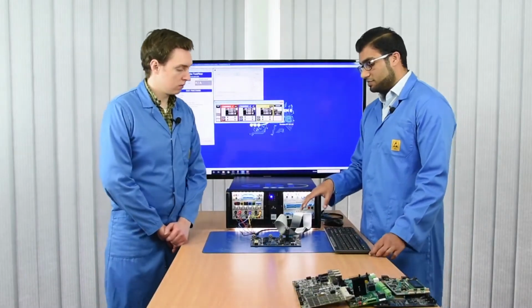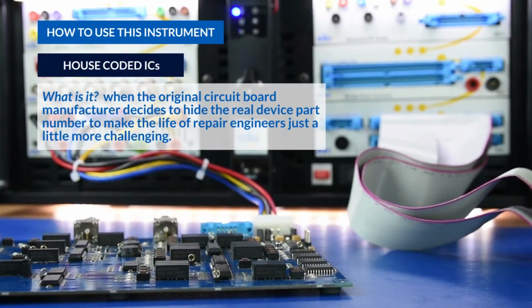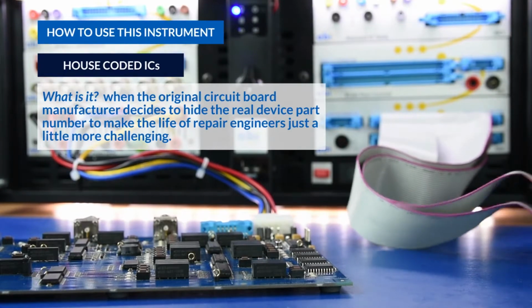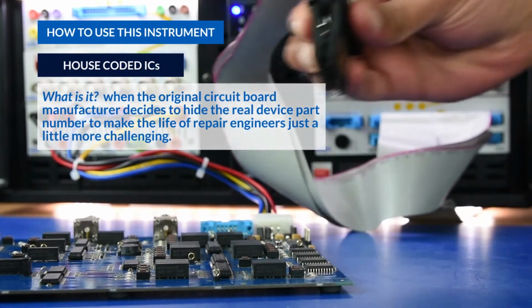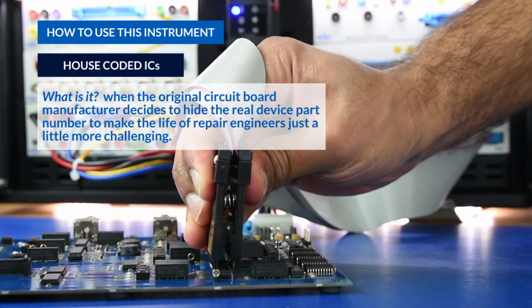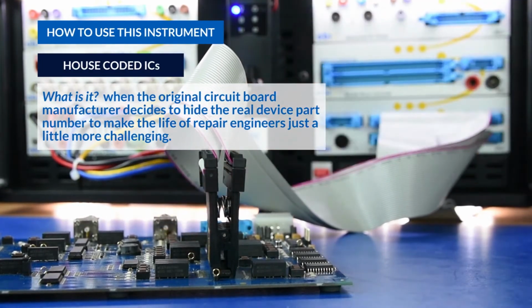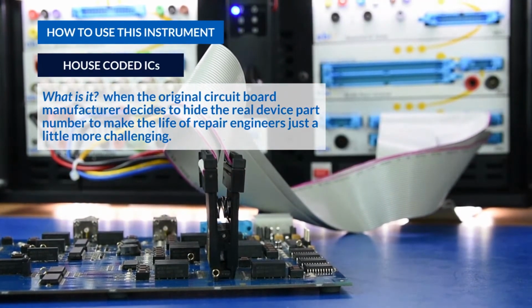And this is very useful, especially when you have house coded devices. For example, it may just say ABB or Siemens or something along the lines of that, so you don't know the specific part number of your device. This is where the instrument comes in handy, so you can find devices that work in the same way as the device you have in front of you.